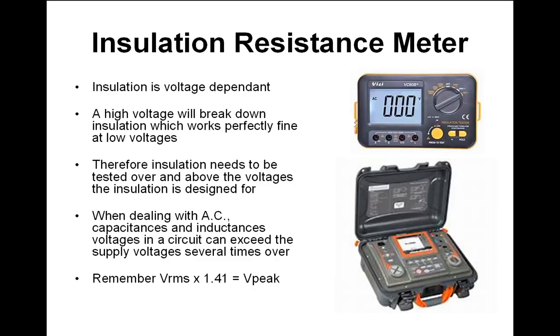Okay. The insulation resistance meter. I'm sure I've done the insulation test with you, and again, it's the same meter you can see there. Also, watch out whenever you do an insulation test: you're using very high voltages and you're using different terminals on your meter than for the low voltage tests. So for example, for a low voltage resistance test, or just measuring a voltage, you use different terminals for that.